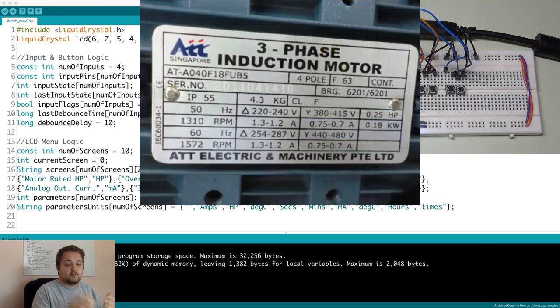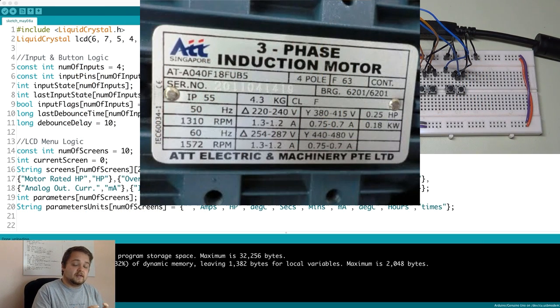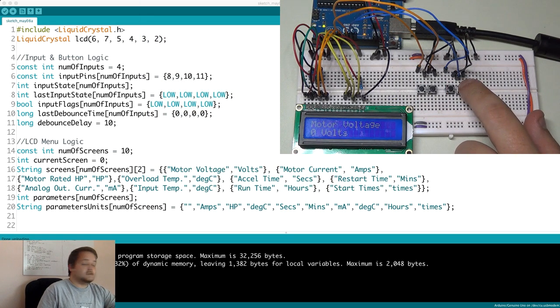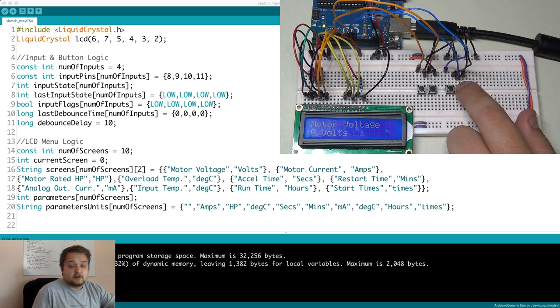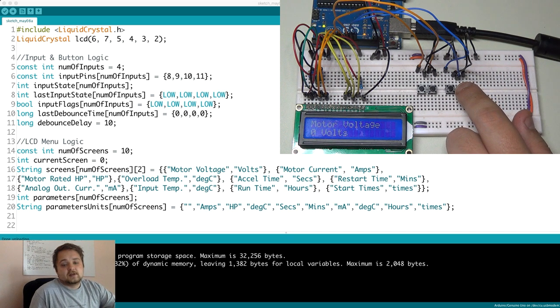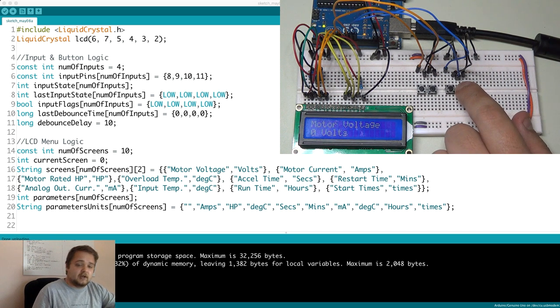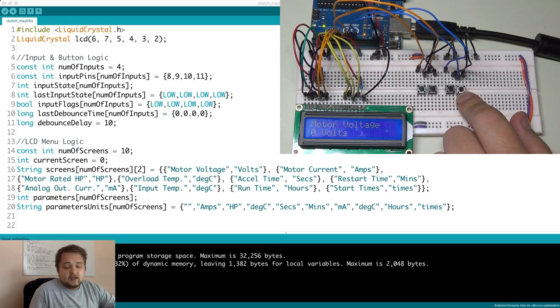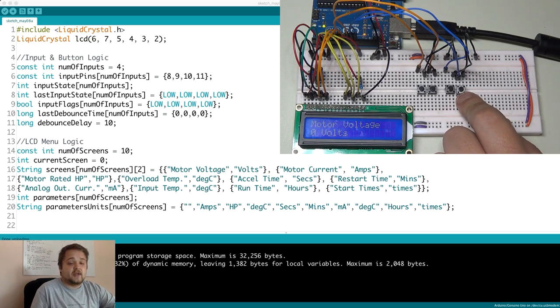So as an example if you plug in a motor and you have a nameplate on the motor you need to enter those variables into the drive. So what you do is essentially set the horsepower of the motor, the rated voltage, the rated current, startup time, acceleration, over temperature, overload protection and things of that nature.